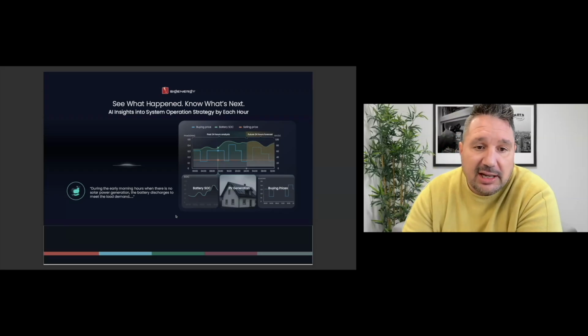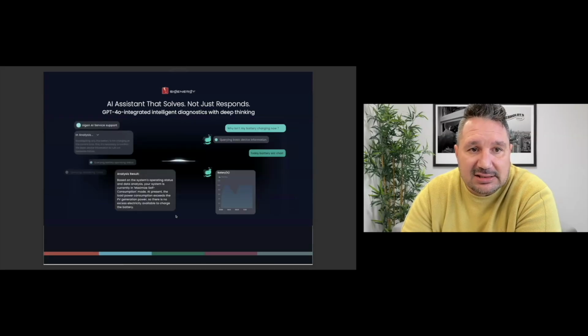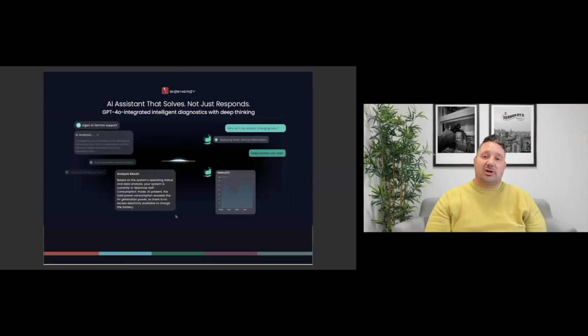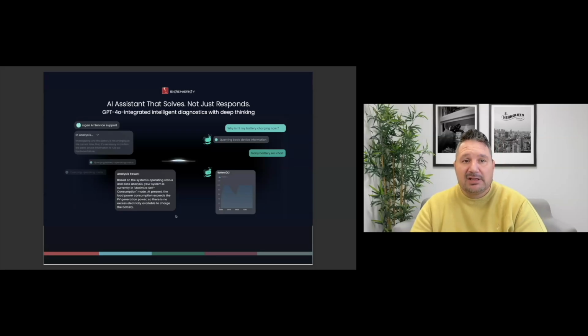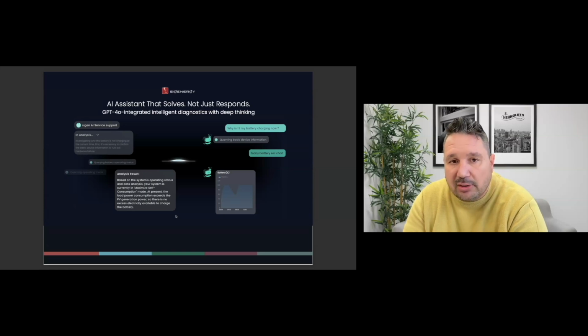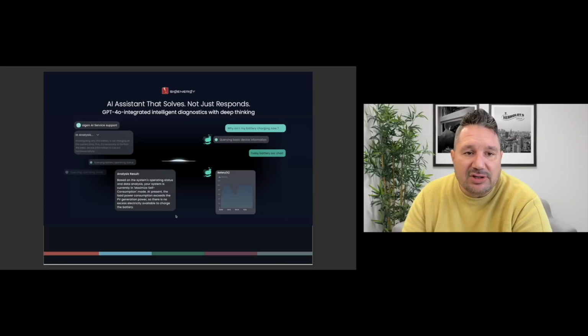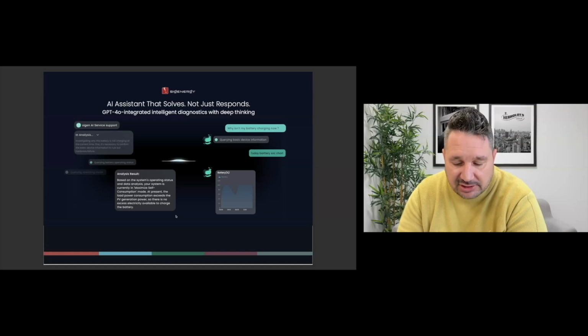When you are using the AI, you can also use it as an assistant. The AI assistant does not just respond, it solves. So GPT-4o integration is built into the SIGEN app. Any installer or any user can just ask the AI, maybe investigate why the battery is not charging at the current time. First, it's necessary to confirm the basic device information, and then it will query the operation status and then reply based on the system's analysis of the operating status. Your system is set into maximize self-consumption mode. At present, the load power consumption exceeds the PV generation power, so there is no excess electricity available to charge the battery.